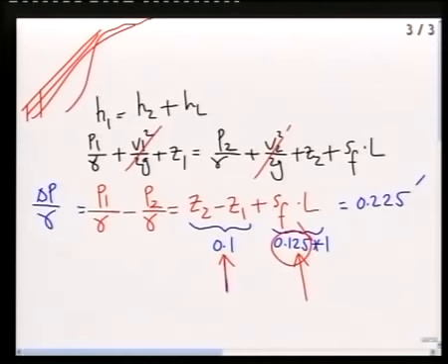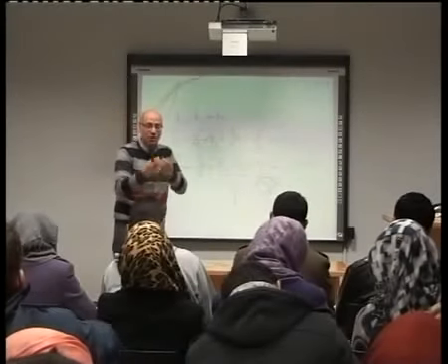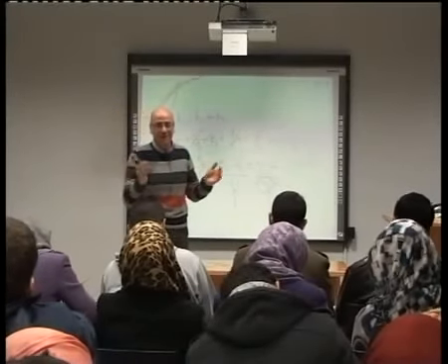by, as we said in the beginning, putting a higher diameter, putting a newer pipe, smooth from inside, things like that. But you can't say I would like to move less flow, because you are requested to move or deliver a certain flow, so you can't also choose that as an option.